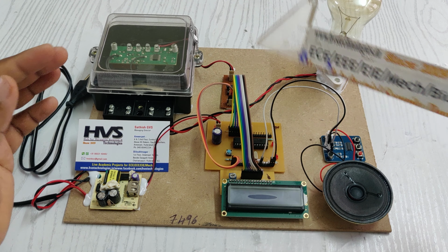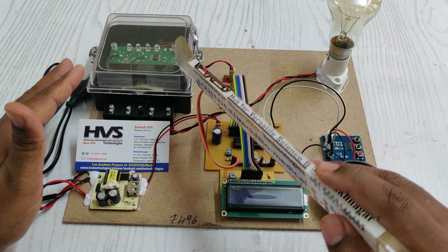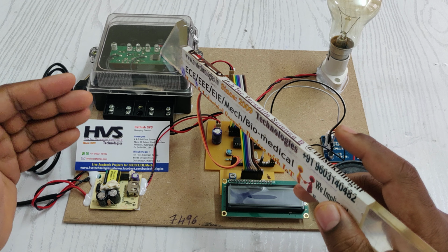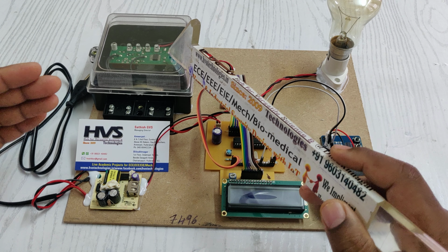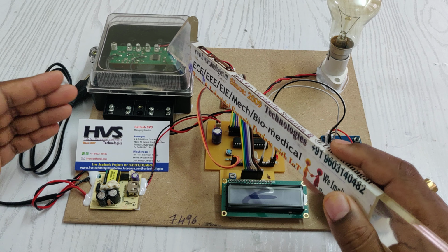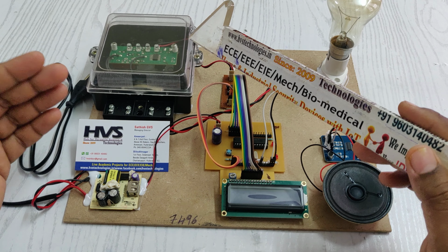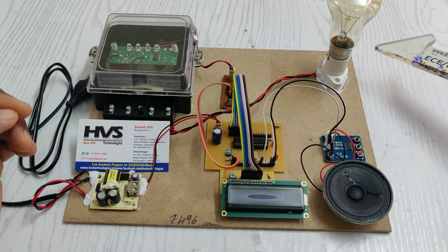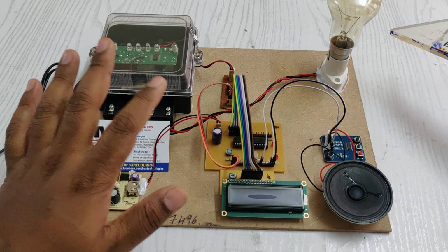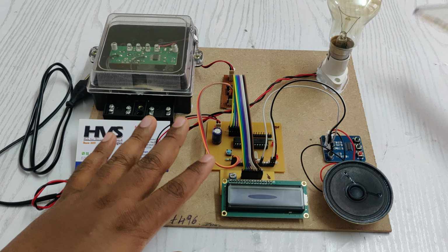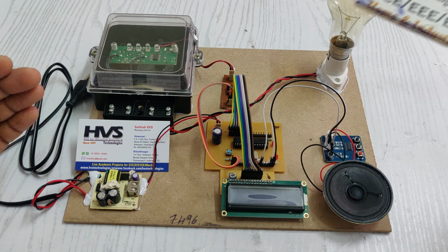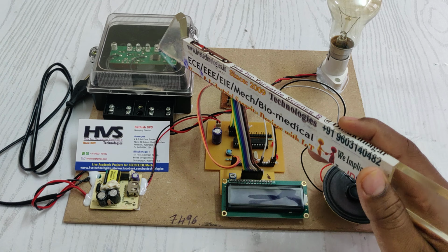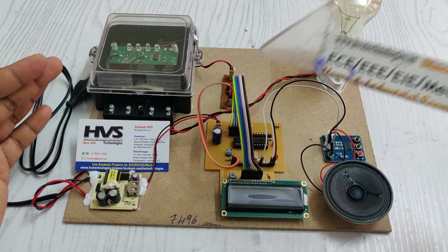According to this energy meter's ratings, if one blink happens, then the energy is 1 by 3200 kilowatt hour. That is nothing but whenever the LED blinks 3200 times, that indicates 1 kilowatt hour of load was consumed. After the energy meter has measured 1 kilowatt hour of load, here the same thing is, one blink is equal to 1 by 3200 kilowatt hour.